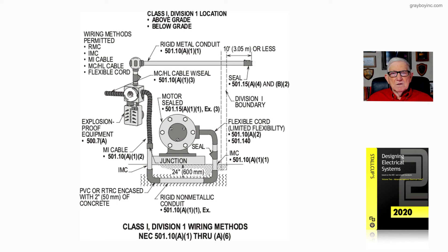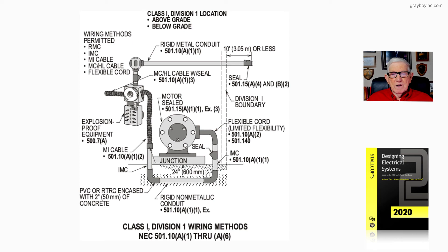These are the wiring methods. The most-used wiring method seen today is the MCHL cable, and you don't need a seal — it uses a fitting listed to seal around the core of the cable and the inside conductors. That MCHL cable is used quite a bit, with rigid now used mainly where needed for physical protection. Figure 21-21 illustrates the wiring methods used in a Class 1, Division 1 location per NEC 501.10A1 through A6.